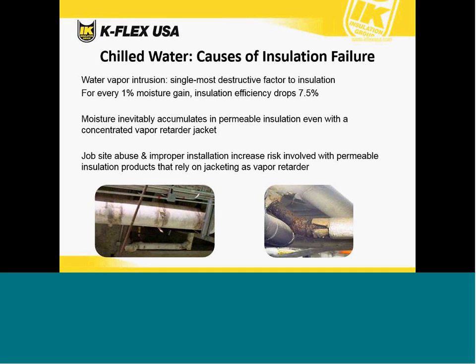Vapor intrusion is the single most destructive factor to insulation. For every 1% moisture gain, the insulation efficiency drops by 7.5%. Moisture inevitably accumulates in permeable insulation, even with a concentrated vapor retarder jacket. An improper installation also increases the risk involved with permeable insulation products, with jacketing as a primary vapor retarder. So down here at the bottom are some things that we're probably all very familiar with. You see some mold growth coming through that white all-service jacket here on the left. Now you see where insulation was cut away, possibly to repair a fitting or replace an insulation system, and then the insulation was not repaired or put back, corrosion that you see there on the right. These are things that can potentially be avoided with a closed cell insulation that doesn't allow moisture to penetrate through and into the insulation system.